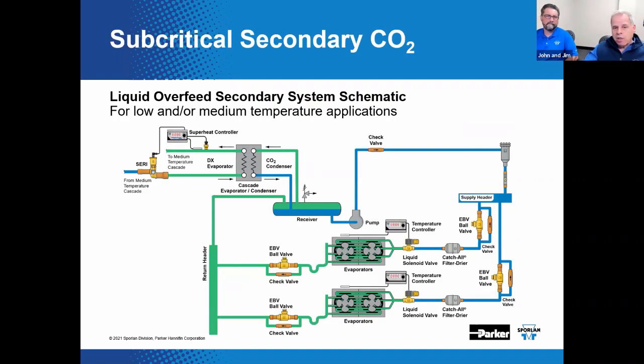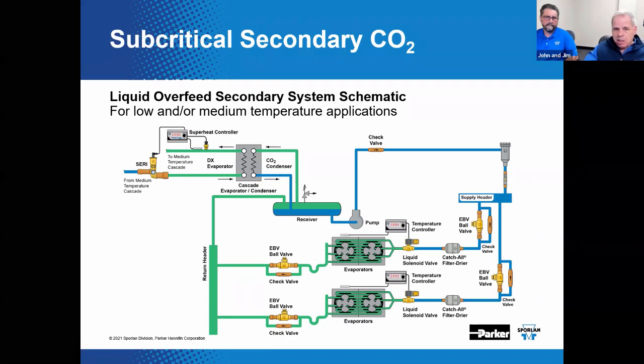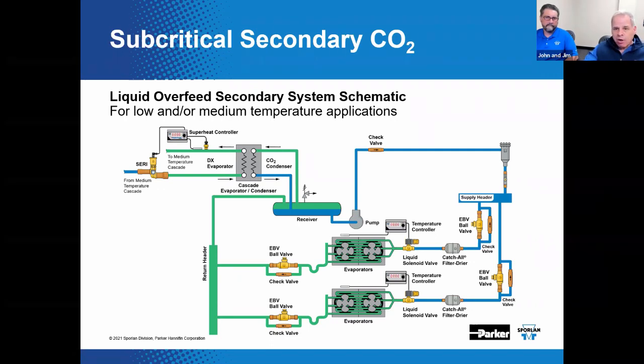Now, this is the liquid overfeed secondary system. Now, it's considered liquid overfeed because the evaporators are flooded, or if you say it another way, more refrigerant is being delivered to the evaporators here than is actually being evaporated, hence the overfeed. Secondary system because the primary refrigerant in the refrigeration plant is not being circulated to the caseload. And what, we'd have CO2 come into the caseload here? Yeah, yes. Because the primary refrigerant in the refrigeration plant is not being circulated to the caseload.